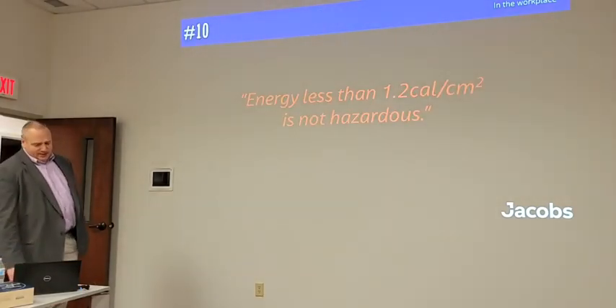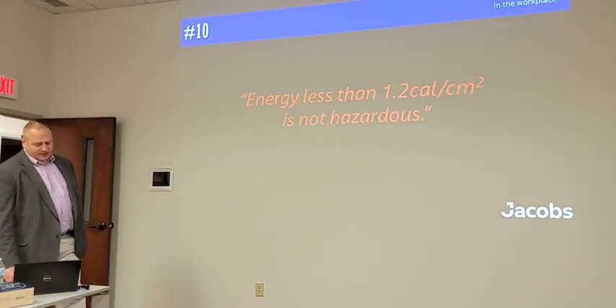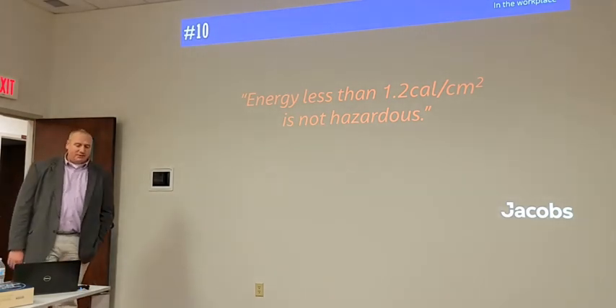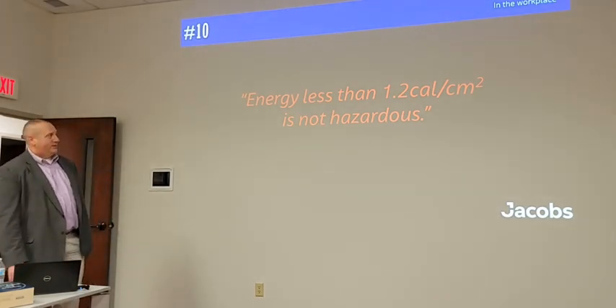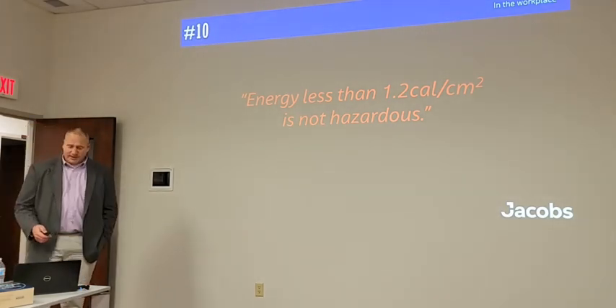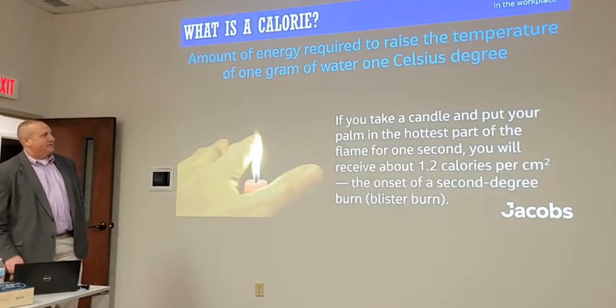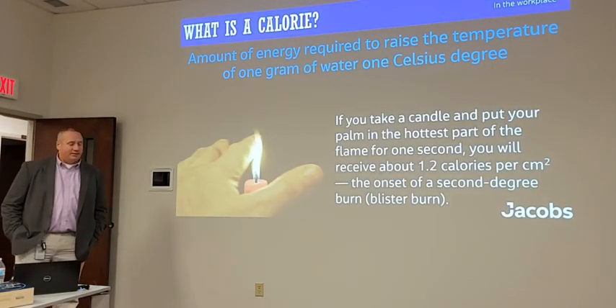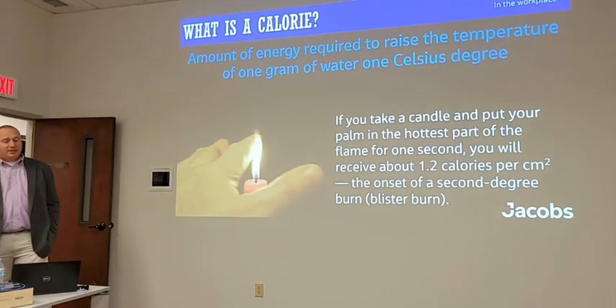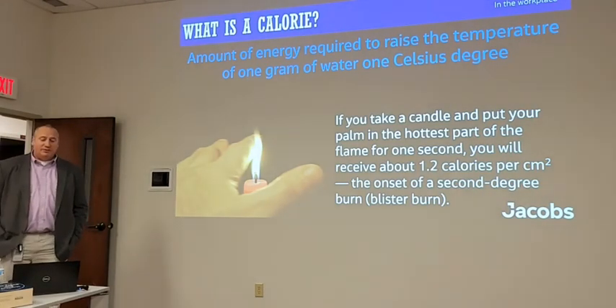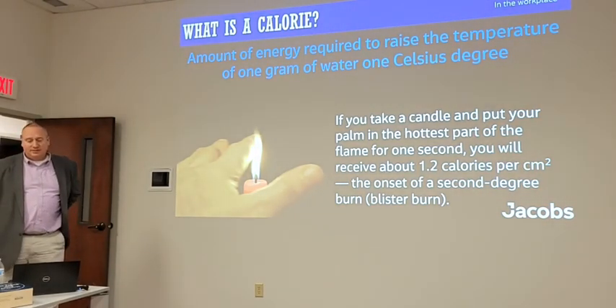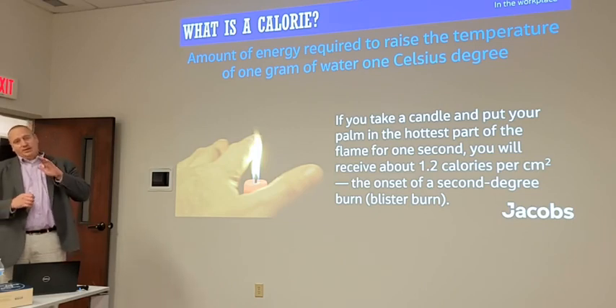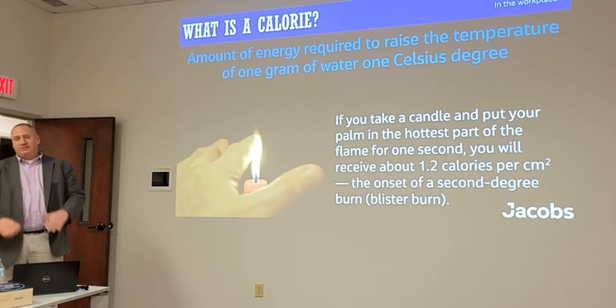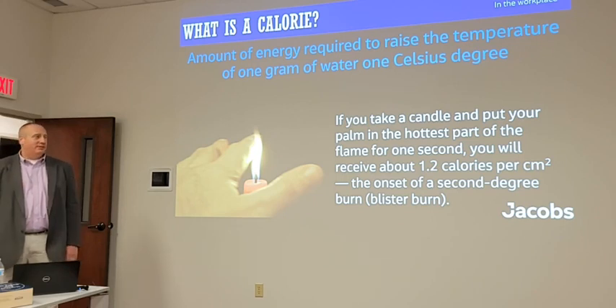And the next one is that energy less than 1.2 calories per centimeter squared is not hazardous. And so to talk about that, what exactly is a calorie that we're talking about here? The calorie is the amount of energy required to raise the temperature of 1 gram of water 1 Celsius degree. And that's if you take your hand and put it in the hottest part of a big lighter flame for about 1 second, you just received about a 1.2 calorie per centimeter squared burn.